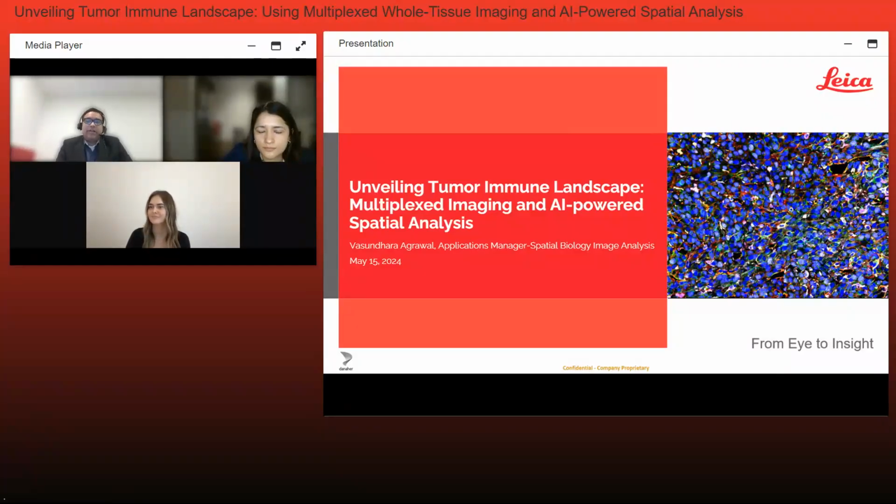Another advantage of CellDive is associated with a robot which is called the bioassembly bot. So you can actually process multiple slides at a time. You can load all your slides inside the robot, program the slides, and load all your antibodies and all the reagents like PBS, mounting media, and dye inactivation solution. Then you can start the robot and just leave the lab, and next morning you come and you see everything is done. So that's a big advantage of CellDive, which can process 15 slides at a time with the help of a robot.